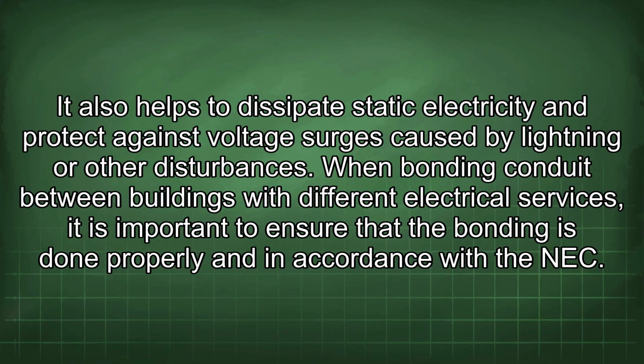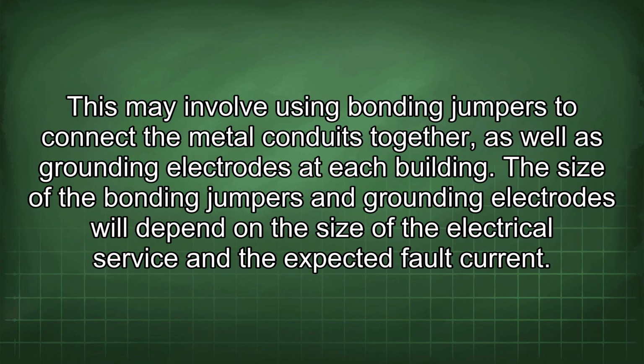When bonding conduit between buildings with different electrical services, it is important to ensure that the bonding is done properly and in accordance with the NEC. This may involve using bonding jumpers to connect the metal conduits together, as well as grounding electrodes at each building. The size of the bonding jumpers and grounding electrodes will depend on the size of the electrical service and the expected fault current.